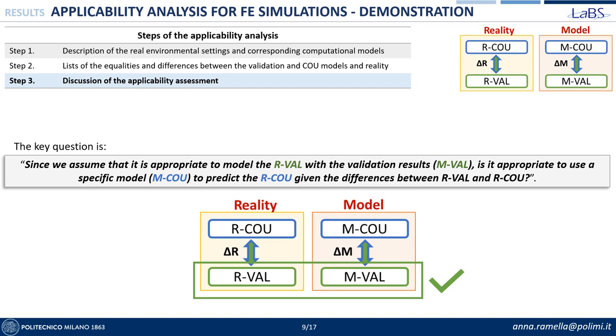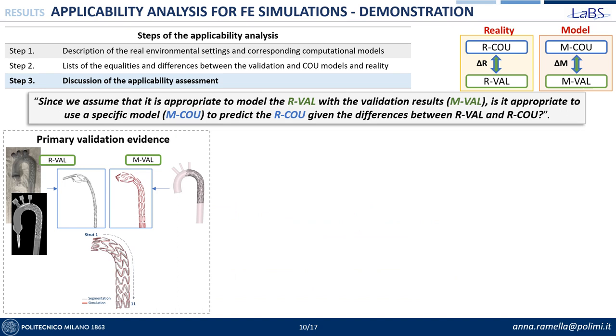Given this, the key question of the applicability assessment is: since we assume that it is appropriate to model the real validation with the validation models, is it then appropriate to use a specific model of the context of use to predict the reality of the context of use given the differences explained before? Focusing on the reality and the models of the primary validation evidence, you can see that in the model we have reached a good agreement comparing the model itself with the reality of the experiment, comparing the simulation results in red with the results of the CT segmentation in gray.